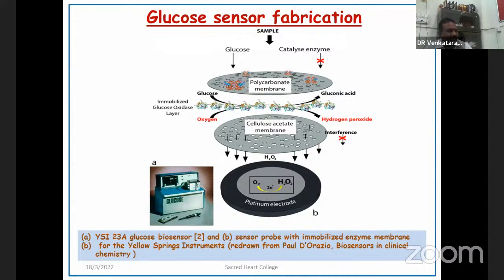So in the first generation sensor, we have the enzyme and we are monitoring the hydrogen peroxide or oxygen concentration. But in the second generation sensor, we put in a metal mediator, like ferrocene complexes, ruthenium bipyridyl, or some inorganic and organic metal complexes, to mediate the charge transport between the glucose oxidase and glucose to enhance the sensitivity of the detection. Why do we need to have the sensitivity?